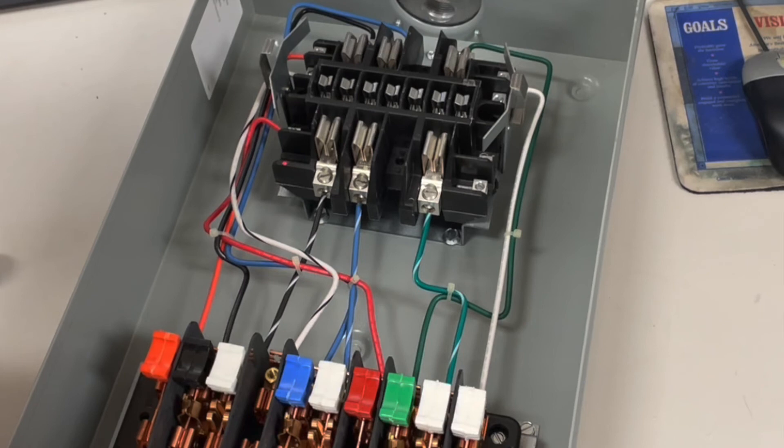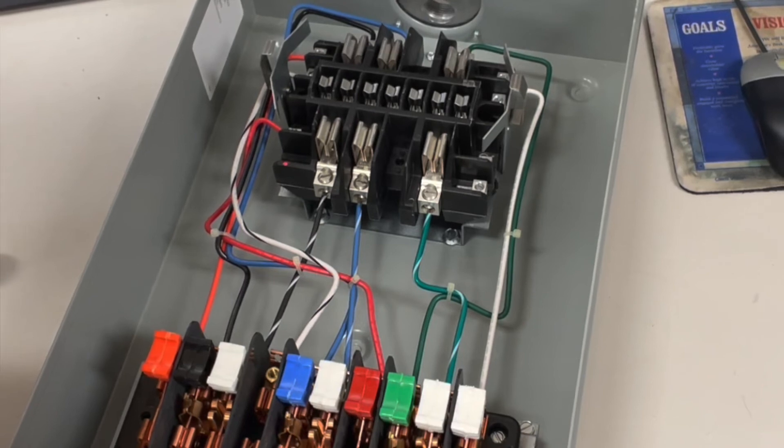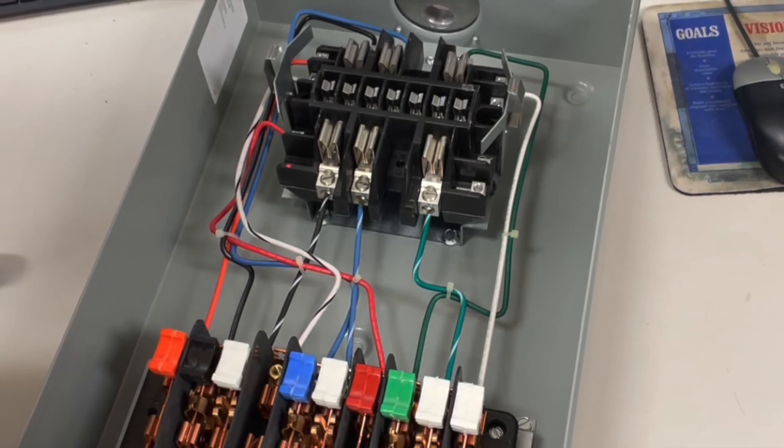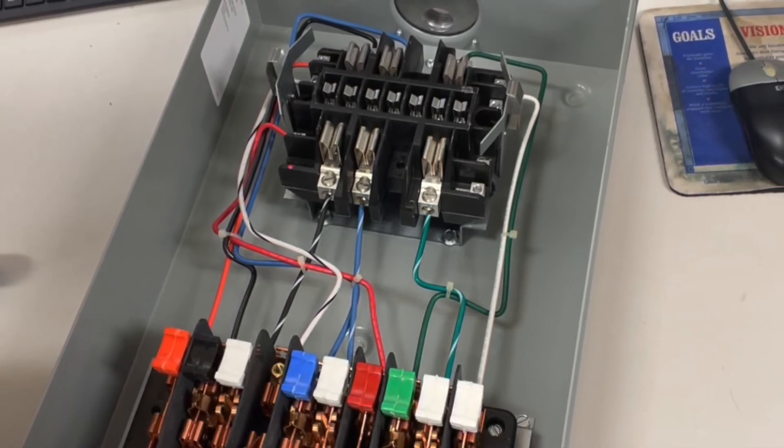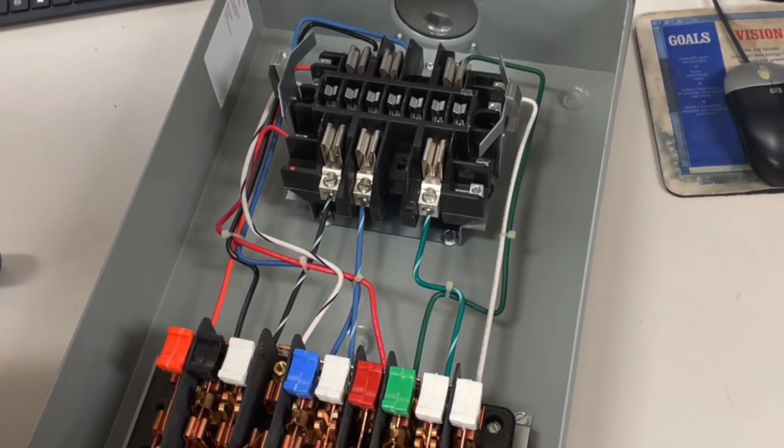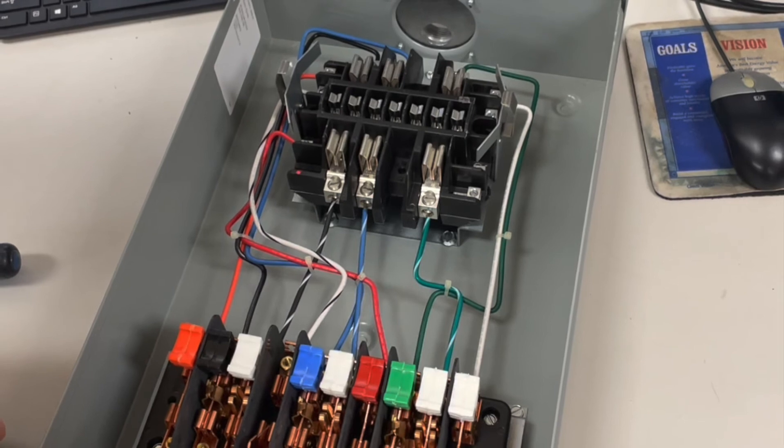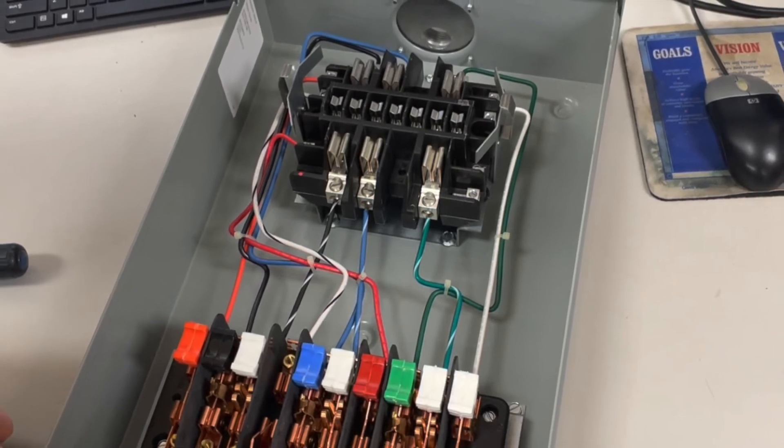Here we had a Form 9 meter in here and we lost a potential tap and we couldn't get the line crew out there to fix it. So we had a Form 6 meter. We said we just go ahead and fix it and get this meter back working and metering the customer correctly. So what had happened here was we lost B voltage.